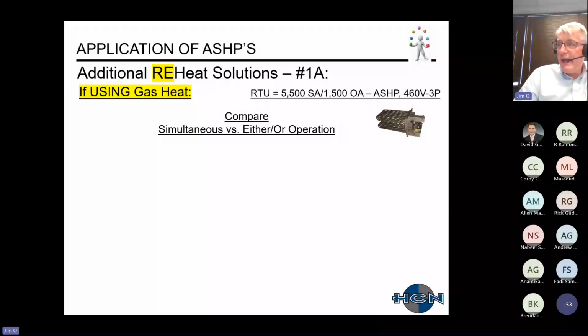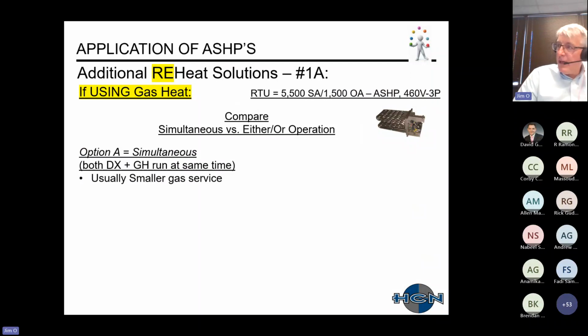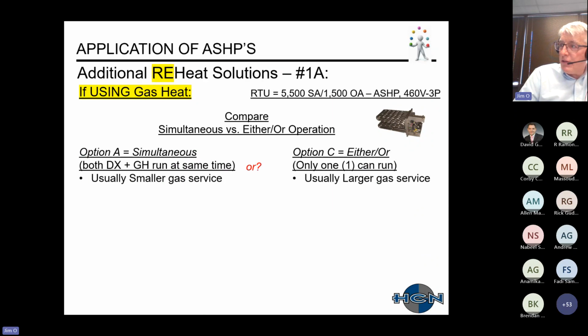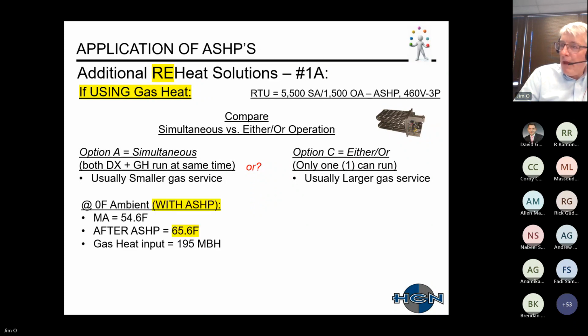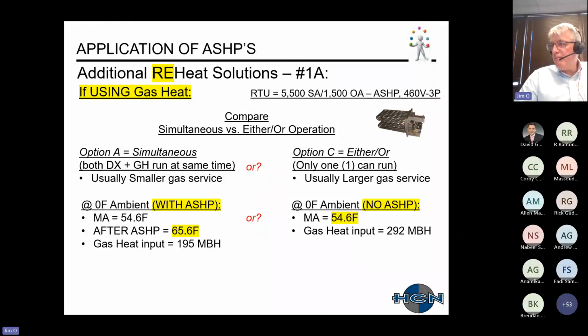All right. So if we're using gas heat, once again, you're going to compare simultaneously versus either or. Usually the simultaneous option has smaller gas service. With option C, the either or, only one of either the gas heat or electric heat can run. If we're using 0 degrees as my design temperature, our gas heater would end up with this output. And then if we have it where the air source heat pump is not operating, therefore we have a lower mixed air temperature, we'll have a higher heating requirement.